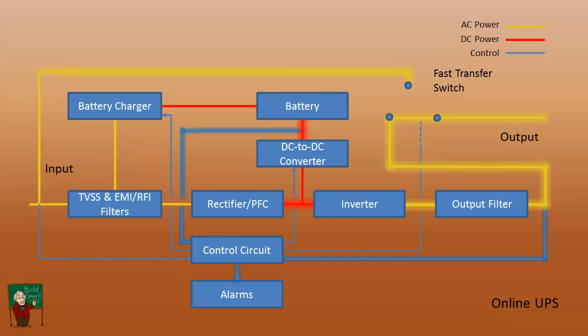If we lose power, you see that there's not a whole lot of change. Nothing really transfers. We have an alarm for the loss of power. Basically, the battery is providing the DC that goes to the inverter instead of the rectifier. So no transfer. There's no break whatsoever in the output voltage.